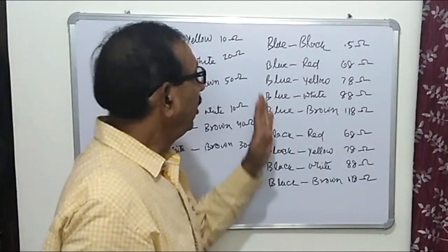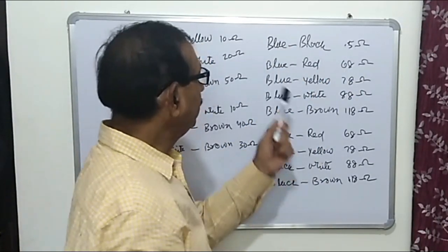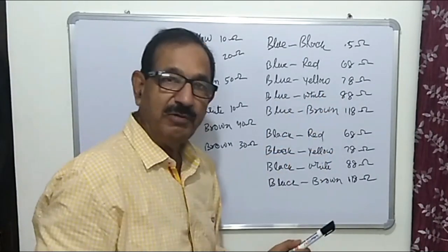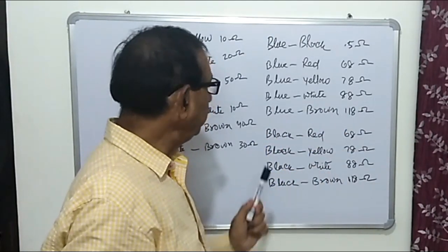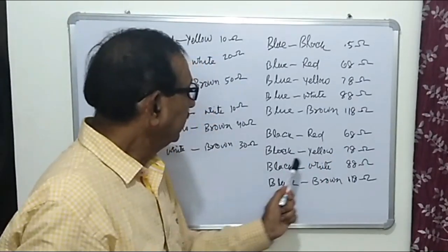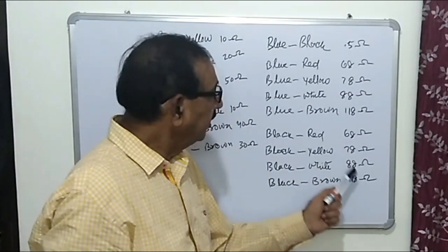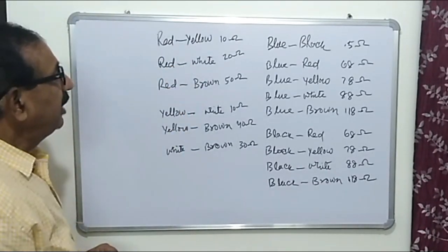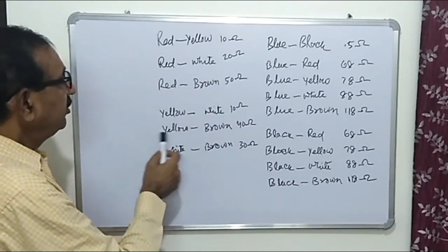After checking all 15 pairs, the results are: blue and black = 0.5 ohm, blue and red = 68 ohm, blue and yellow = 78 ohm, blue and white = 88 ohm, blue and brown = 118 ohm, black and red = 68 ohm, black and yellow = 78 ohm, black and white = 88 ohm, black and brown = 118 ohm, red and yellow = 10 ohm, red and white = 20 ohm, red and brown = 50 ohm, yellow and white = 10 ohm.